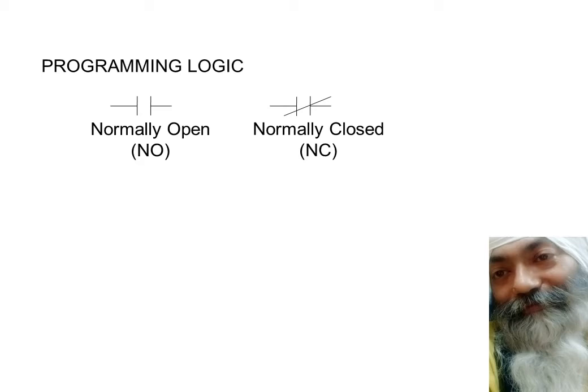NO, normally open. It's normally open when in the de-energized state. The moment it gets energized, it gets closed. Similarly, normally closed means when it is in the de-energized position, it is closed, but the moment it gets energized, it becomes open. You don't call it becoming normally open. Normally it was closed, it becomes open.